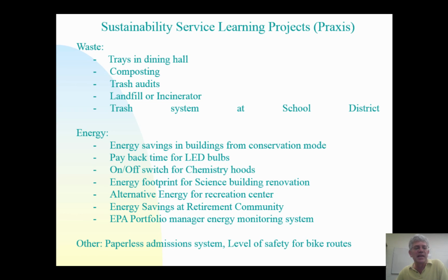They looked at savings for putting LED bulbs into the lights. They looked at how much savings we could get if we put on-off switches on some of the chemistry hoods. Right now, the research hoods don't have any off switches, and so they're in use all the time, even if there are no experiments being done. And that turned out to be a significant energy savings.